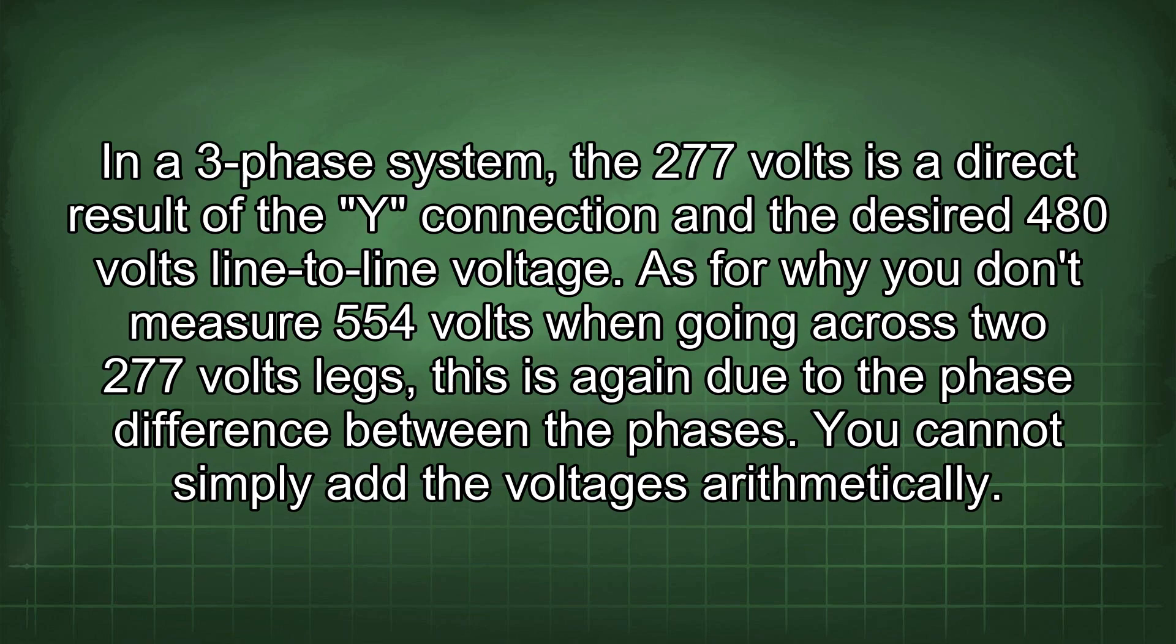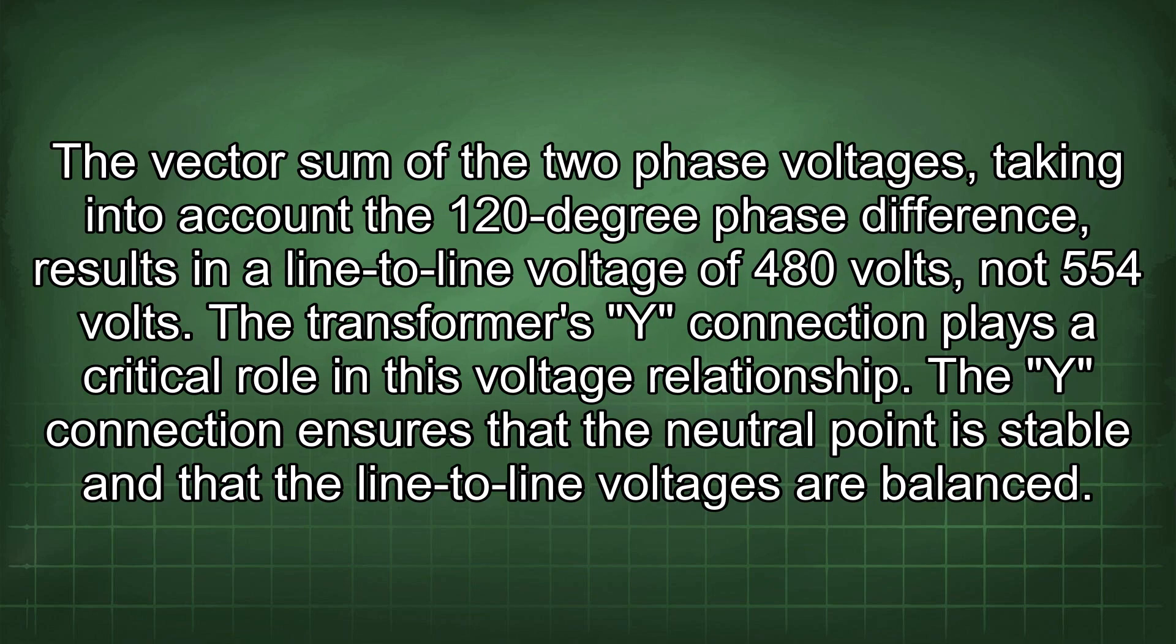In a 3-phase system, the 277 volts is a direct result of the Y connection and the desired 480 volts line-to-line voltage. As for why you don't measure 554 volts when going across two 277 volt legs, this is again due to the phase difference between the phases. You cannot simply add the voltages arithmetically. The vector sum of the two phase voltages, taking into account the 120 degree phase difference, results in a line-to-line voltage of 480 volts, not 554 volts.